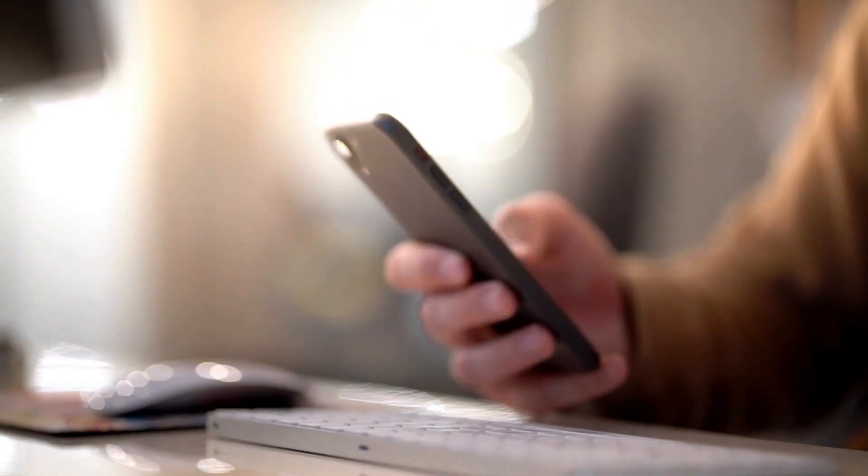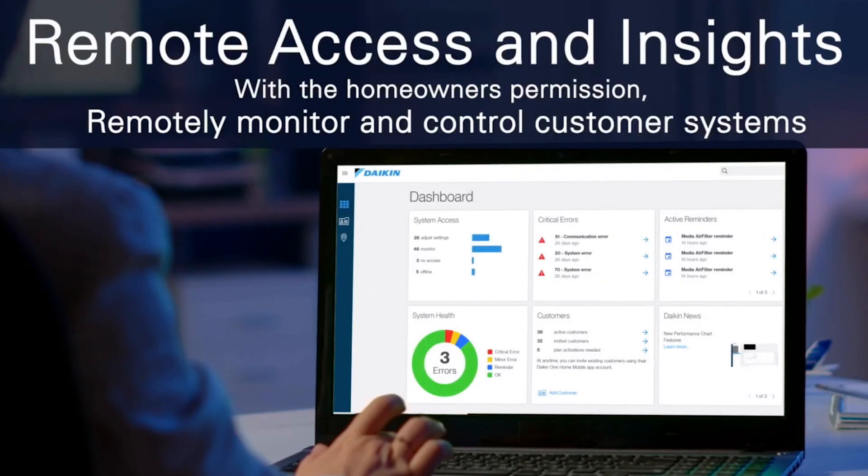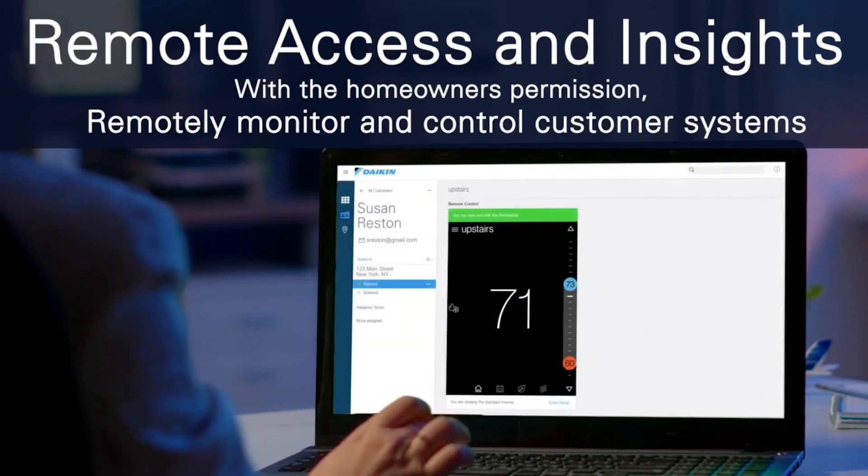You've got the ability to go in and set that system up. Because installers know they're setting the same settings again and again at each install, Quality Install allows dealers to save their own profiles. A contractor can go through, create their own profile, and say this is how I set it up. Even if there isn't a climate optimized profile for their region or microclimate, they can define how every system is set up and configured. And they've got visibility — if something was missed or not done properly, with cloud services a contractor could remotely access that system once the homeowner gives permission and make those changes.